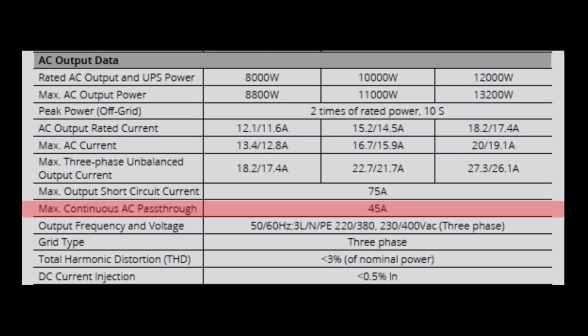is not exceeded. This next line just outlines the tolerances that this inverter has for the various aspects of three-phase electricity. It can use 50 hertz or 60 hertz. 50 is common in Europe and here in South Africa, and 60 hertz is used in the United States. The 3LNPE notation refers to the 3L, which is three line conductors or phases, the N is the neutral conductor, and the PE is the protective earth ground conductor.